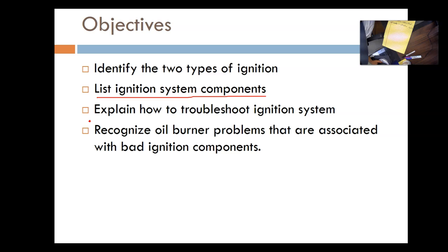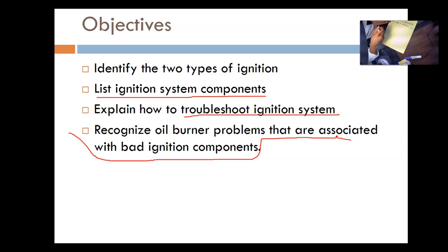Again, gas ignites faster than oil. We'll explain how to troubleshoot the ignition system, what could be the problem with ignition systems. It can be very frustrating if you don't have the right ignition. That could be very problematic because the system will not ignite and it will go in trial 3 times.